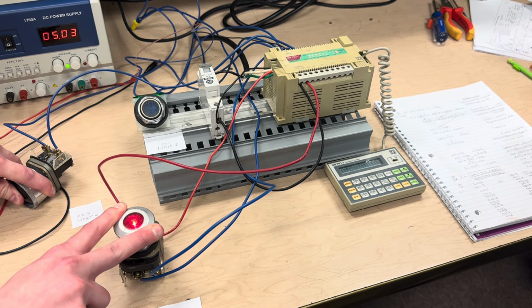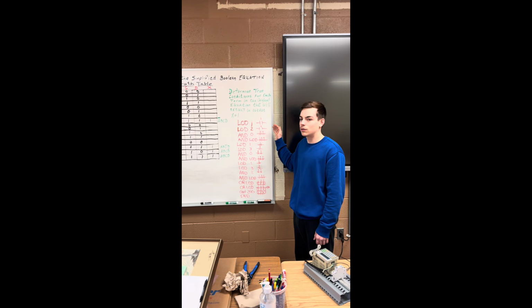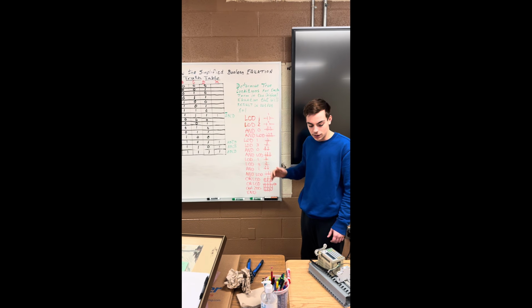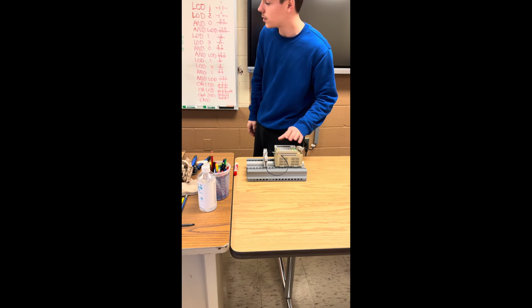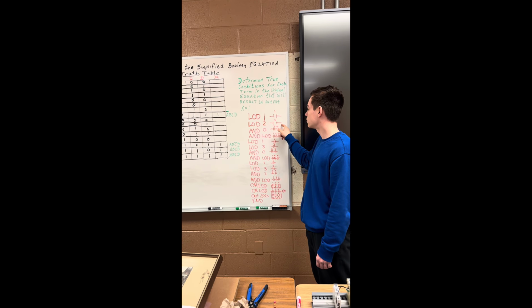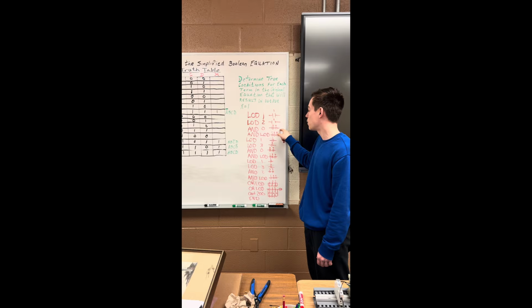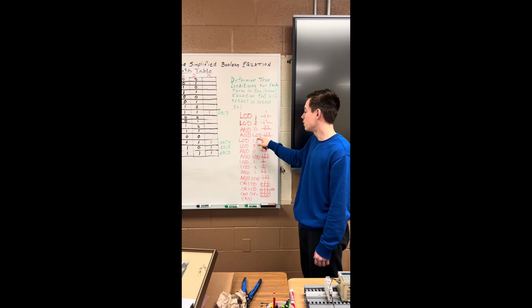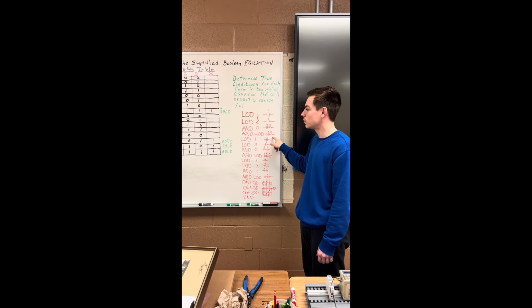So that proves out. Okay, so this is the instruction list, the programming for our actual PLC. It's currently loaded into our PLC. It starts with load 1, and then load 2, and then you AND the 2 and the 0 together to create one line, and then you AND load, which will then combine all 3 of these into one separate line for our first true statement.